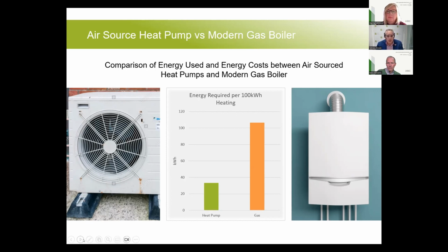It's quite difficult to get exact COPs from the manufacturers, as they only really want to talk about the seasonal. But I've managed to get from Mitsubishi, on one of their machines, some figures which are useful to look at. When it was -7 outside, which again isn't very often, this particular machine dropped down to 3 to 1. When it rose to -3, it was 3.4. At 0, it was 3.7. At 1 degree it's 3.9. And at plus 25, it was running at 5. So again, you think about your hot water loads, which often are more than your heating. If you are starting to achieve 5 to 1, maybe 6 to 1 in the real summer, you can see how much cheaper this machine is to run than a gas boiler.